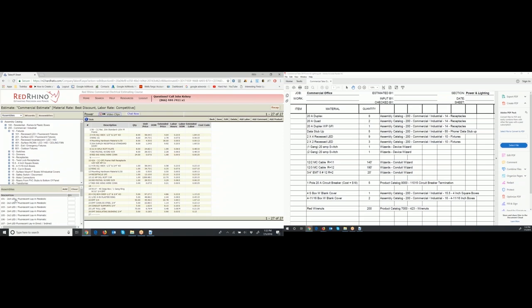We're looking for 2x2 and 2x4 recessed LEDs, so click on 101 recessed LED. The top two items in the list are a 2x4 LED with parabolic lens and a 2x2 LED parabolic lens. The labor for 2x2s and 2x4s is mostly the same, with the exception of emergency fixtures. For the takeoff sheet showing nine 2x4s and three 2x2s, click Add and populate to the right. Notice it shows the fixture with a zero for the dollar amount — fixtures need to be quoted separately and input into the estimate.